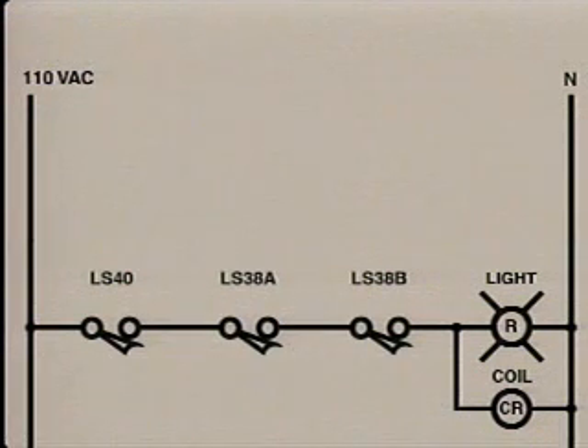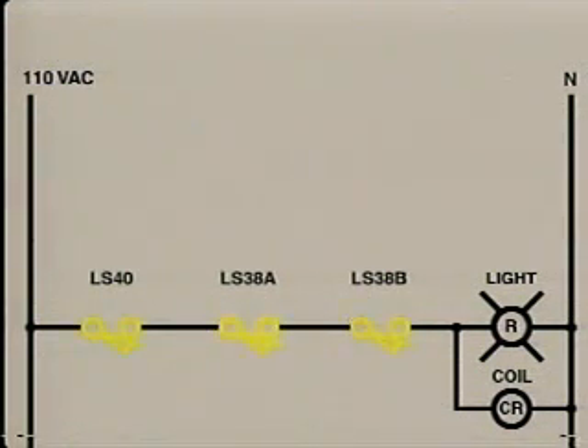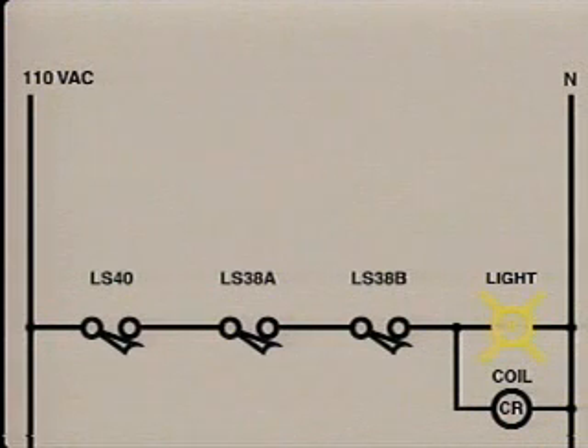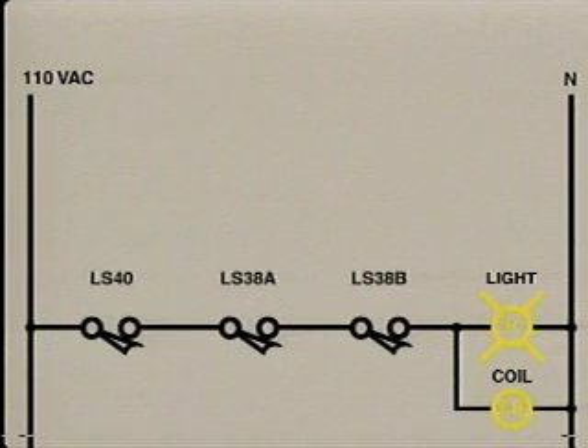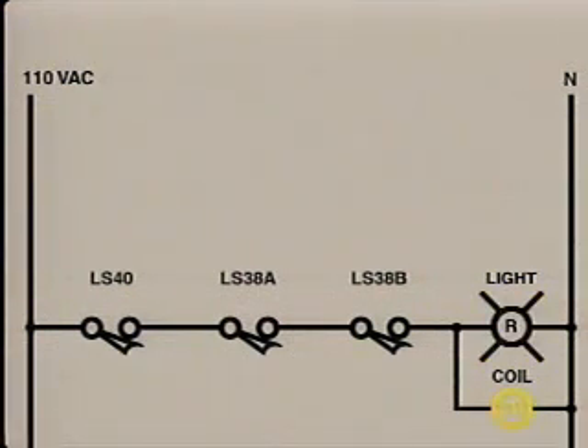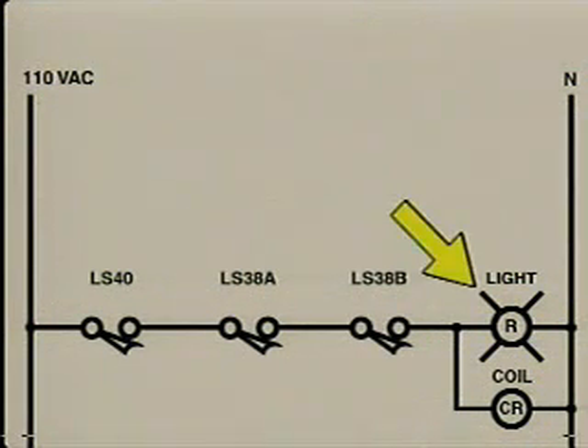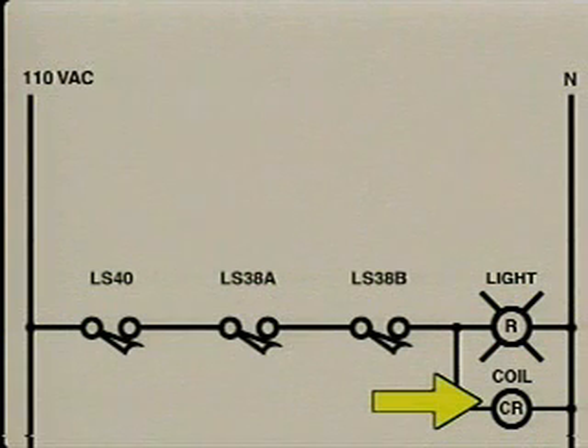When the process is operating properly and all 3 limit switches are closed, the silo crossover indicator light comes on and the control relay's coil is activated. When the control relay's coil is activated, the control relay's contacts are also activated. This change in the state of the contacts allows other devices in the process to operate. In this situation, the electrician knows that when the crossover is attempted, the indicator light does not come on, and other devices, which are partially controlled by the relay, are not activated.